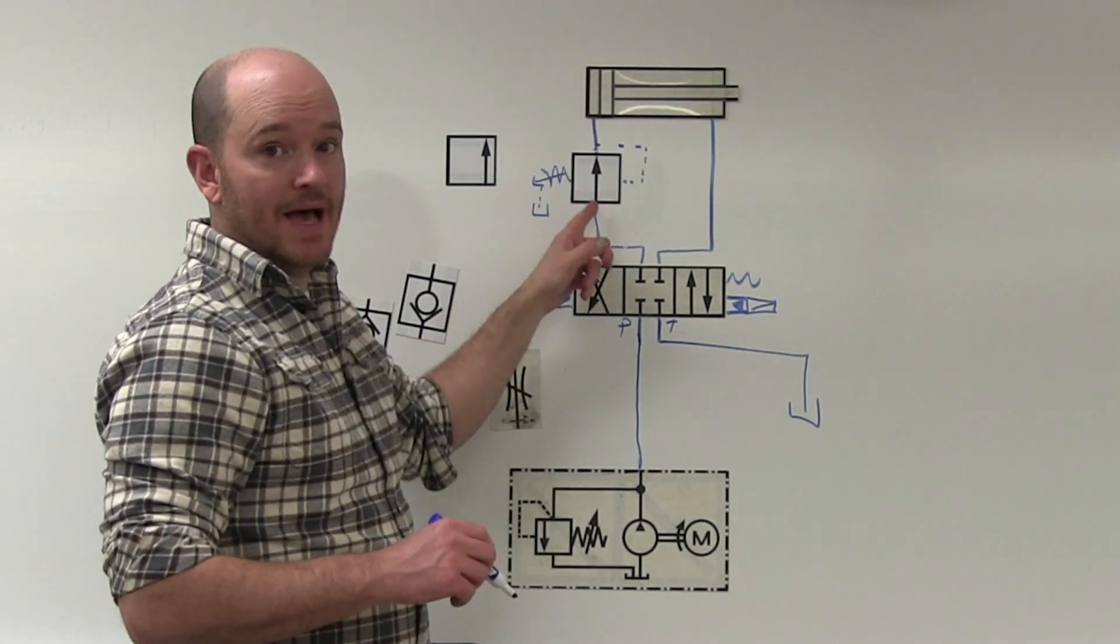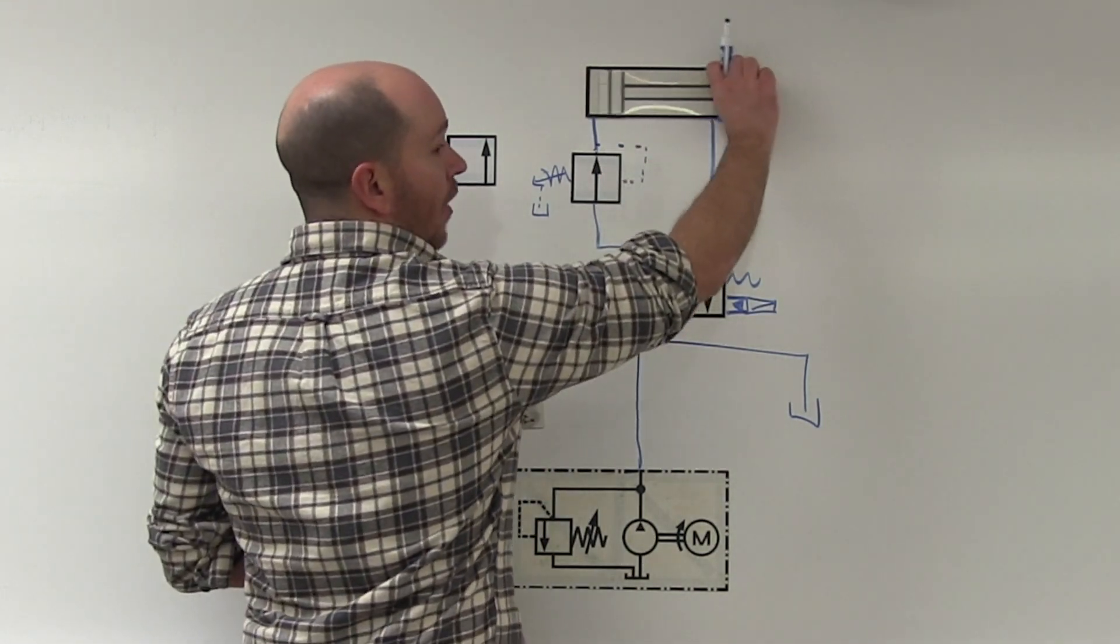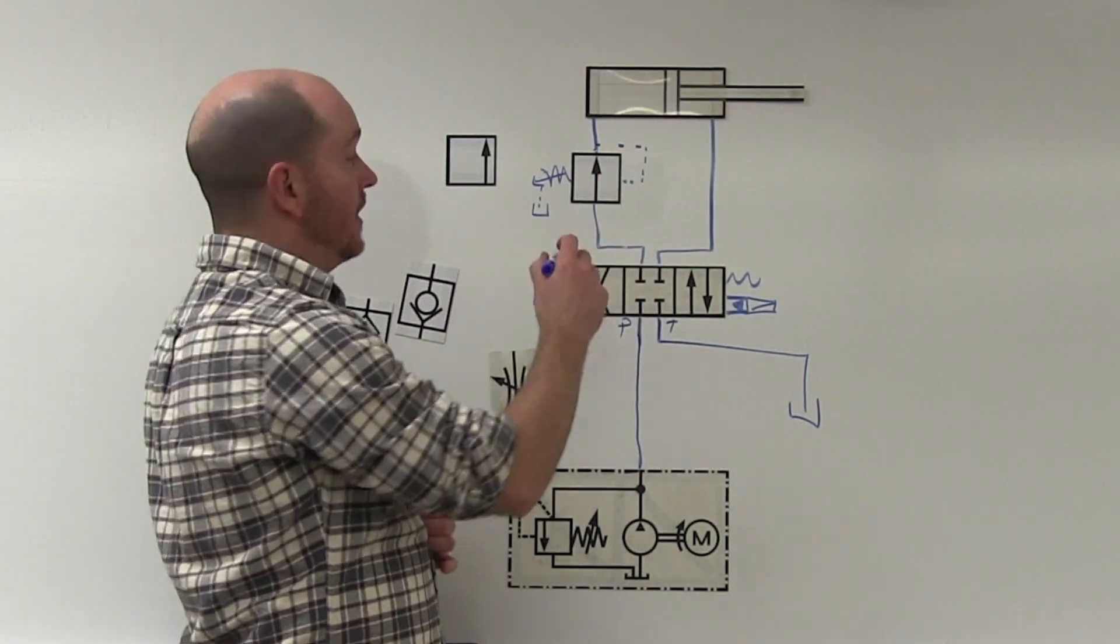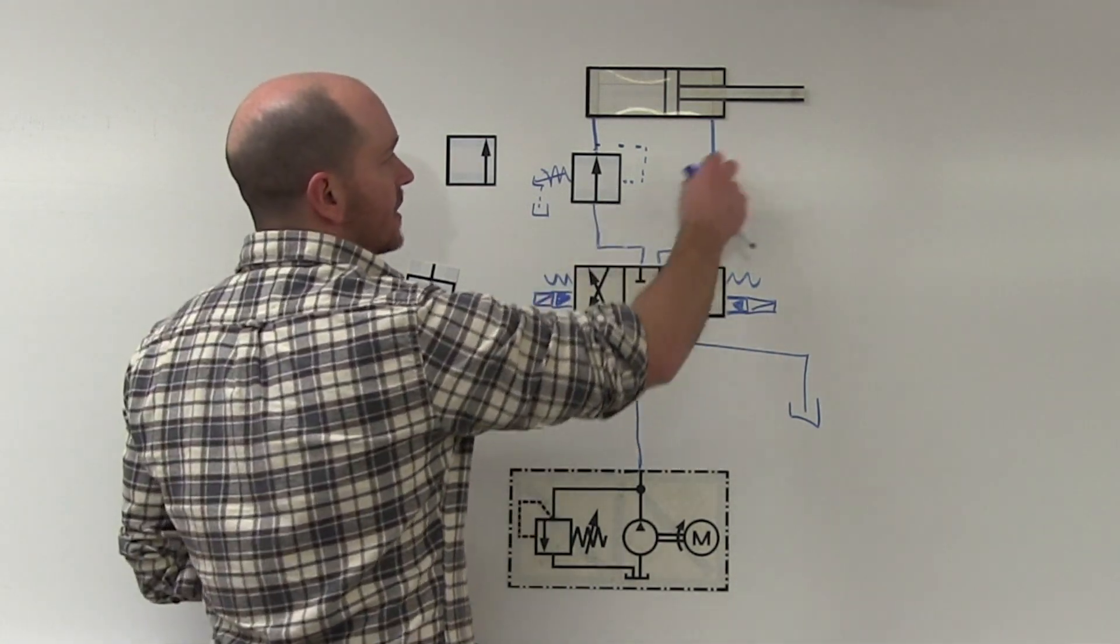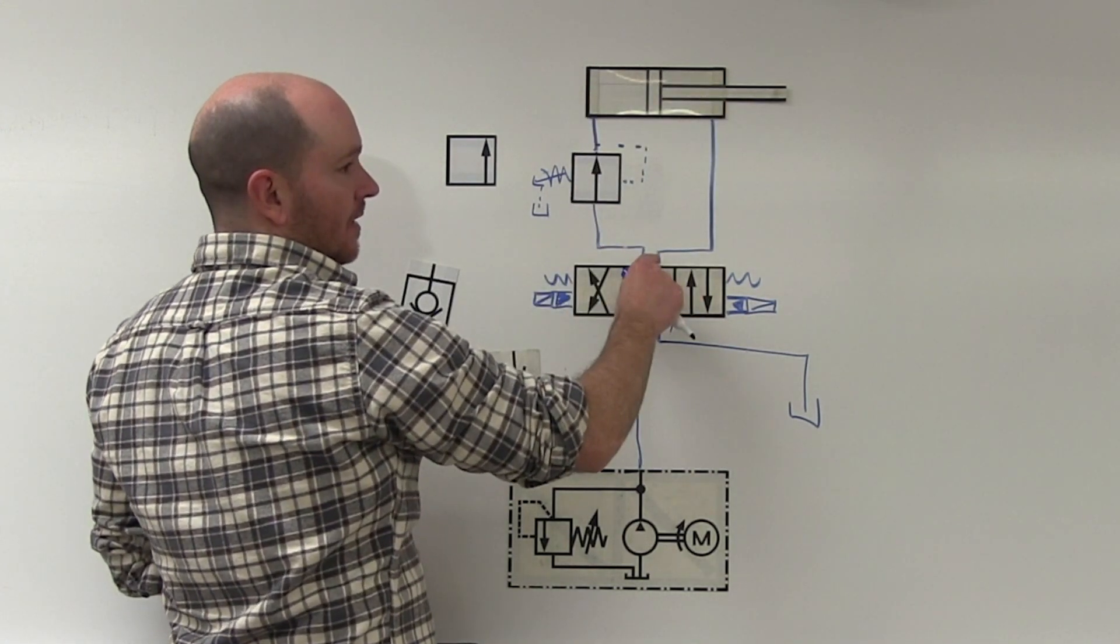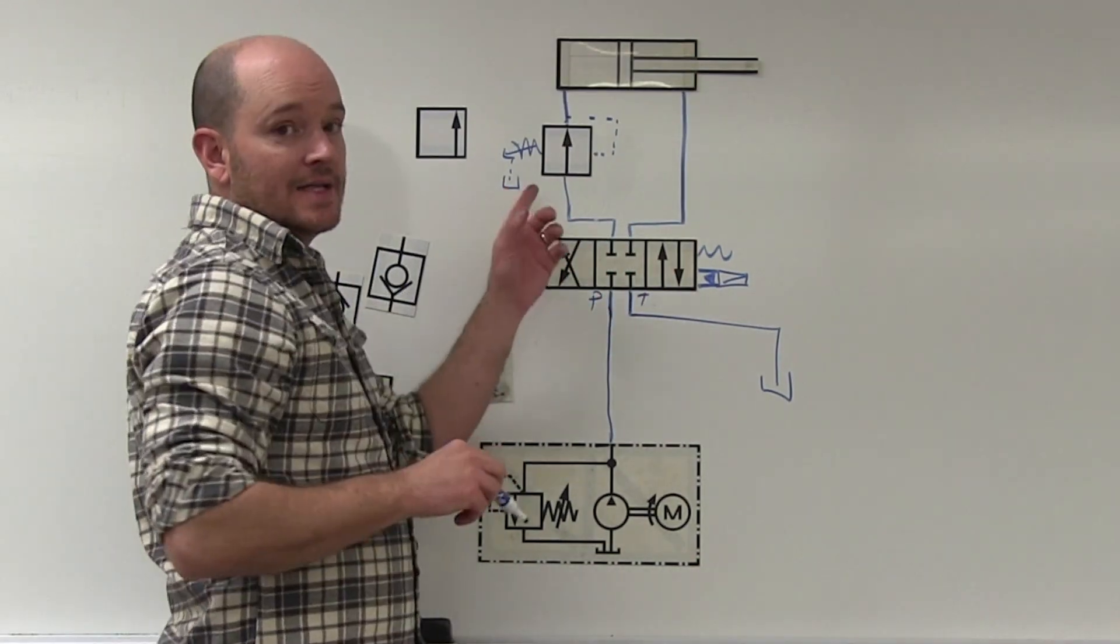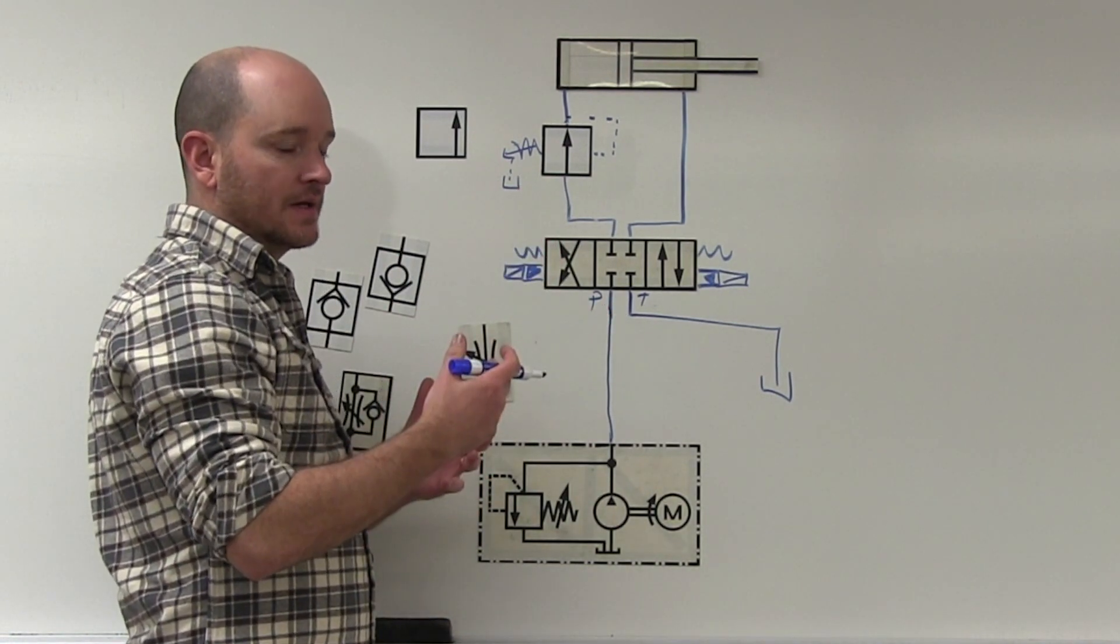I don't need a bypass check valve here because this is normally open. So on most valves, when you're using a normally open one, which is basically your pressure reducing valve in hydraulics, when it comes back, it has a path to come through here. So it does not require a bypass check valve, unlike the flow control valve that we talked about before.